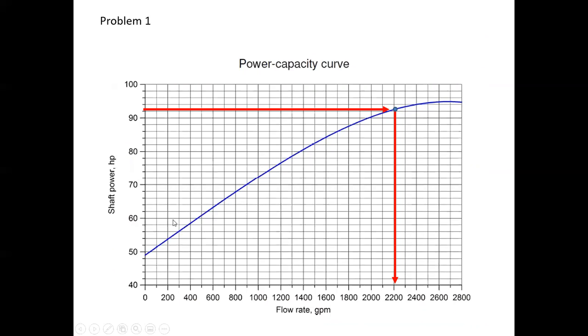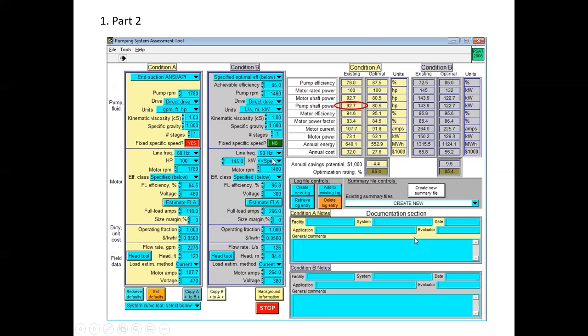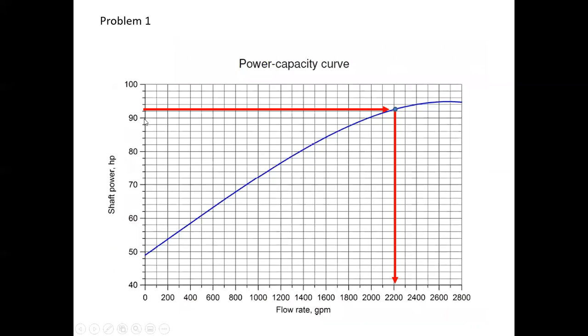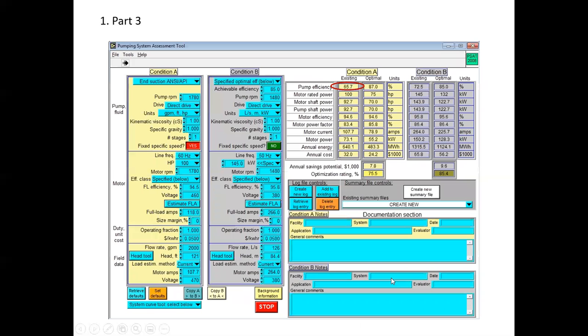Okay, and so this is the power capacity curve. So I've got shaft power over here. And so what was that number? 92.7. So there's 90, 92, 94, so someplace in there, however you want to draw it, over, put a dot, and then down. And so this would predict a flow a little over 2200. I think I have done this once before, and I think I got 2230 that time. Someplace probably 2210 to 2220. Probably 2210 is probably better based on looking at this curve, but at any rate.